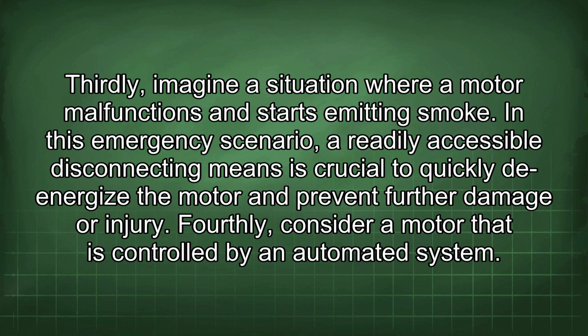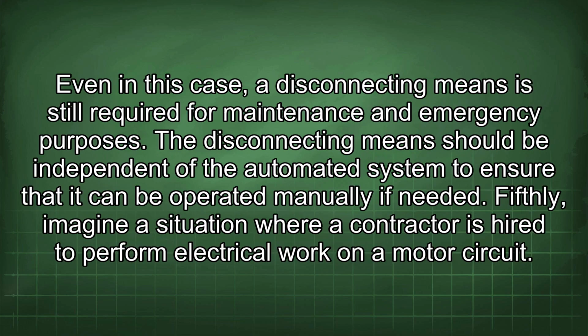Fourthly, consider a motor that is controlled by an automated system. Even in this case, a disconnecting means is still required for maintenance and emergency purposes. The disconnecting means should be independent of the automated system to ensure that it can be operated manually if needed.